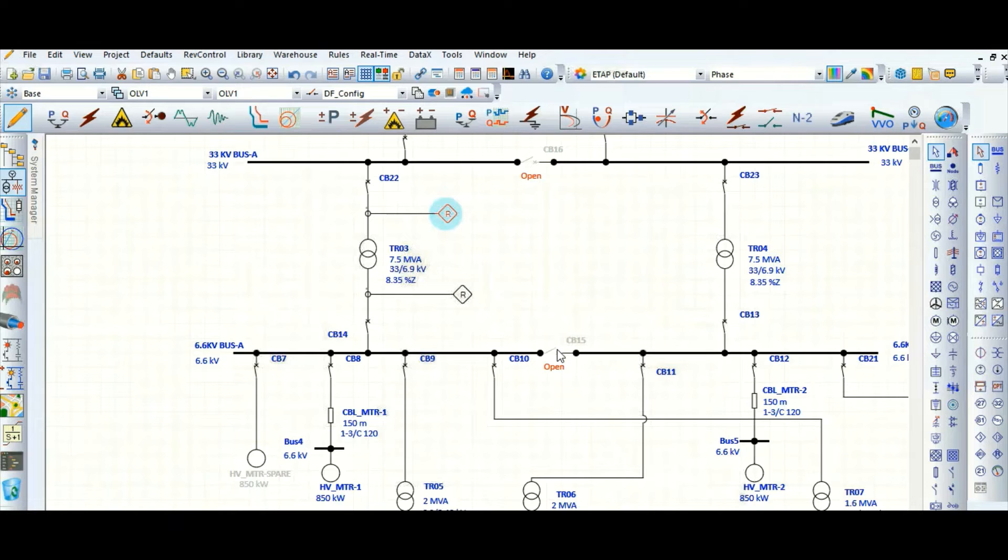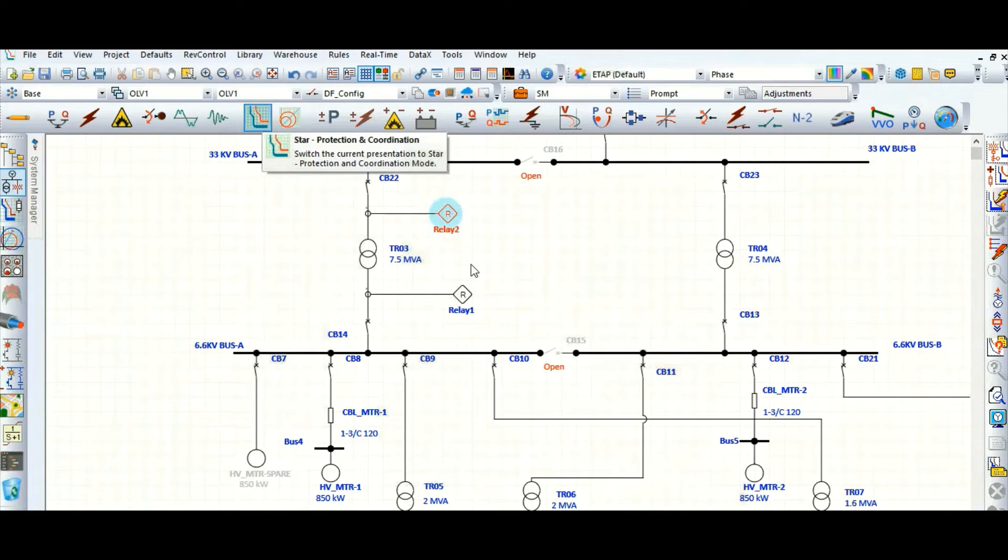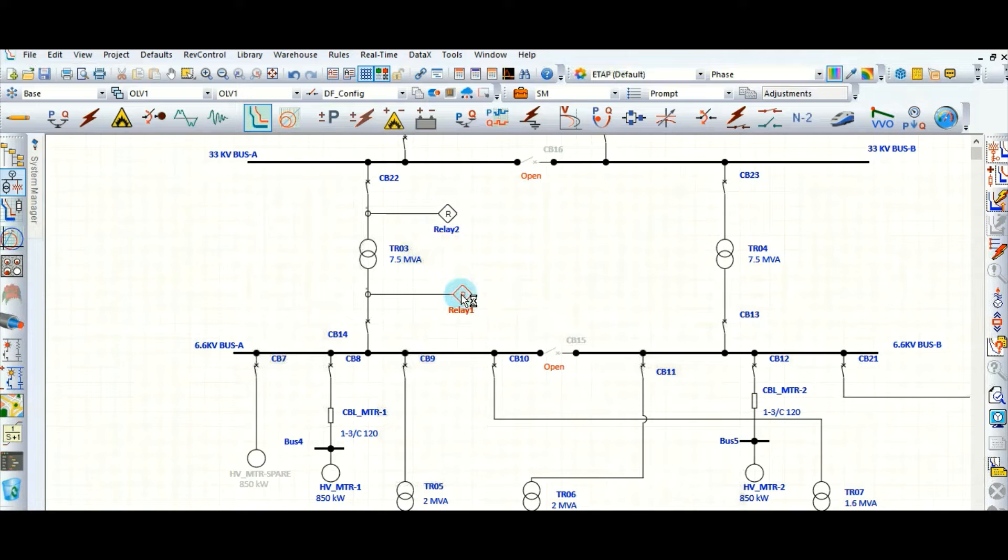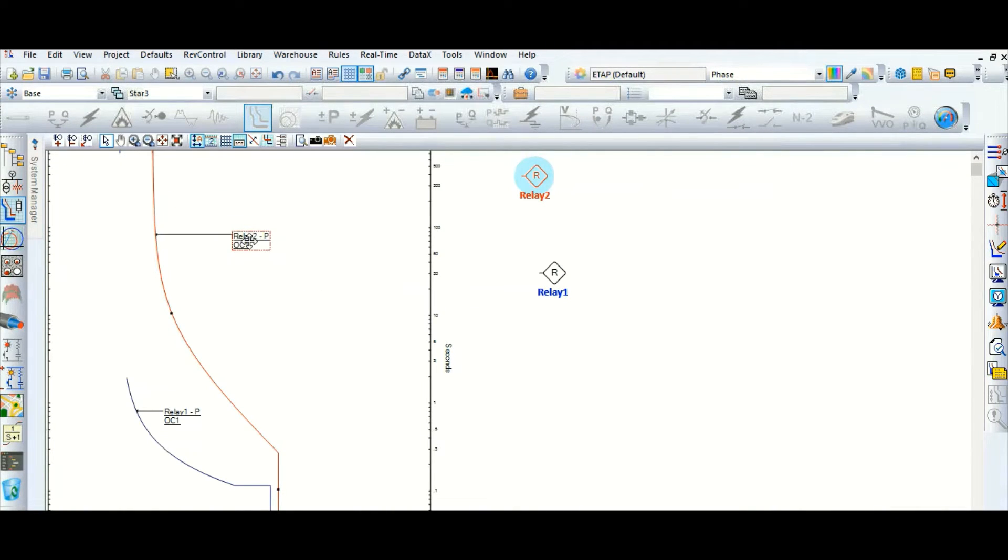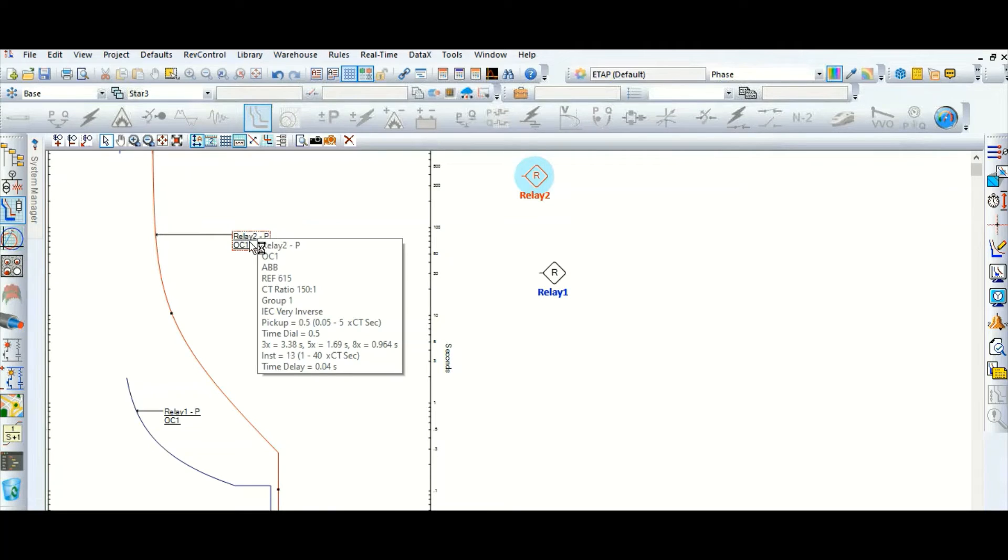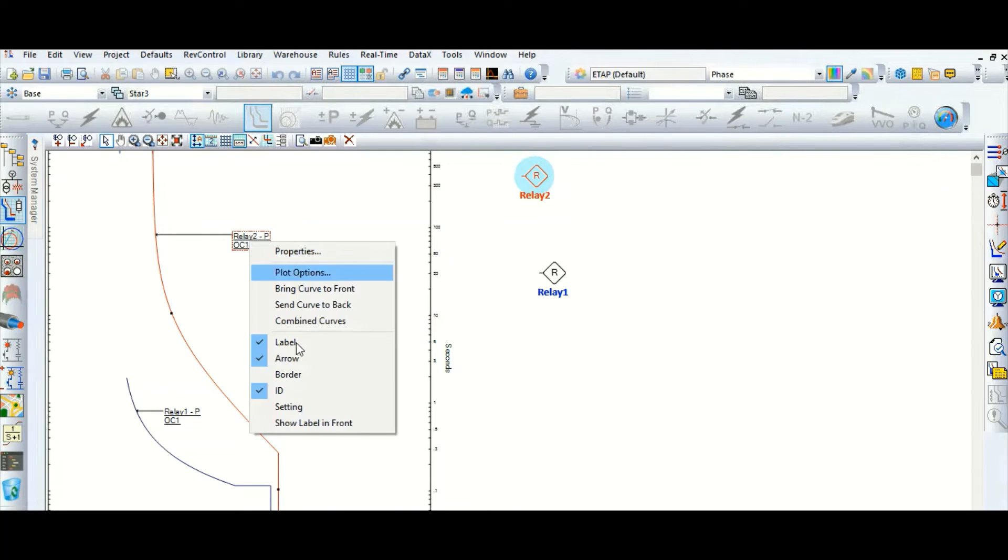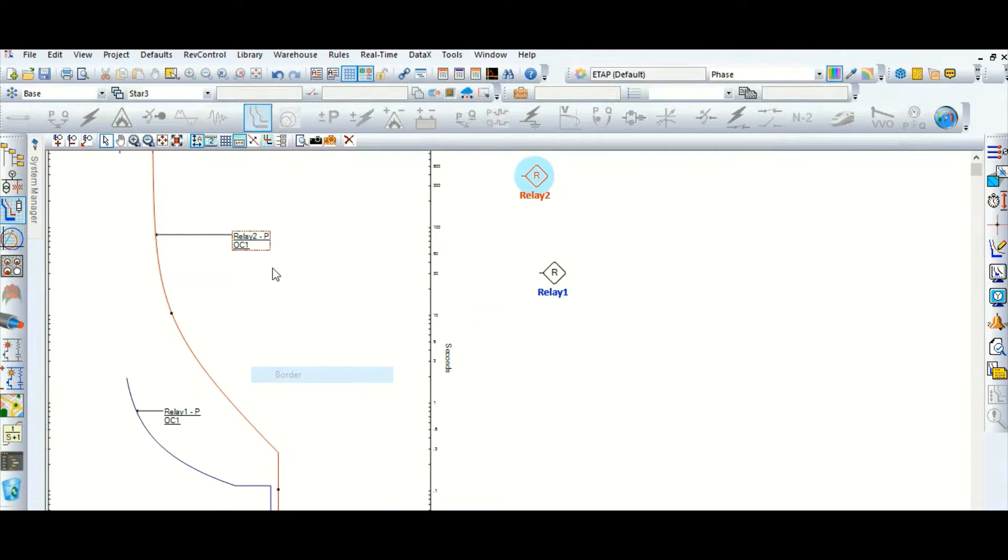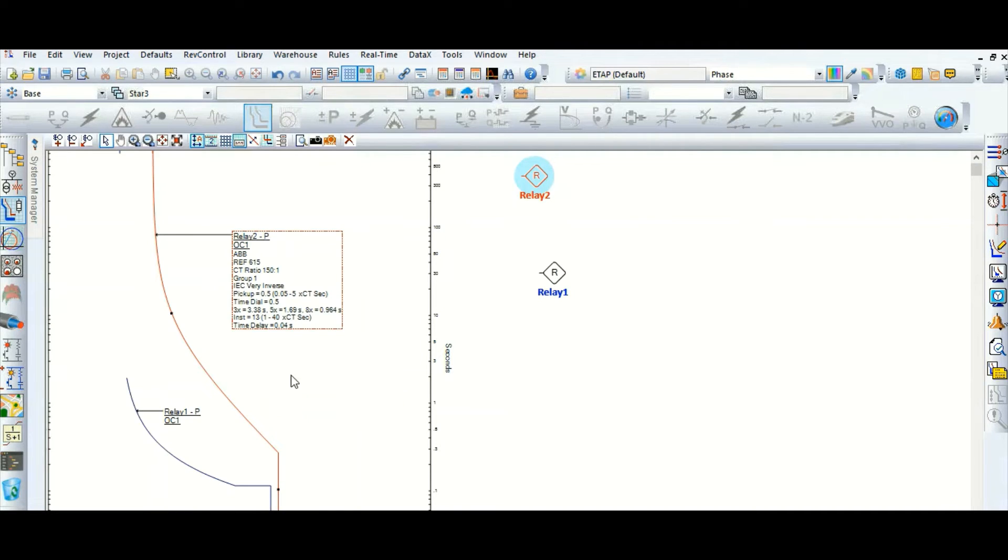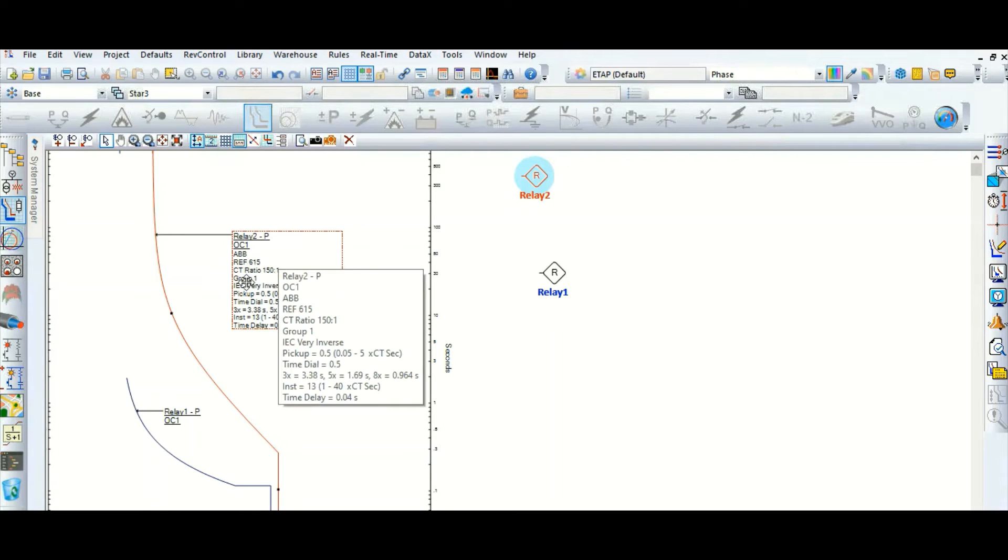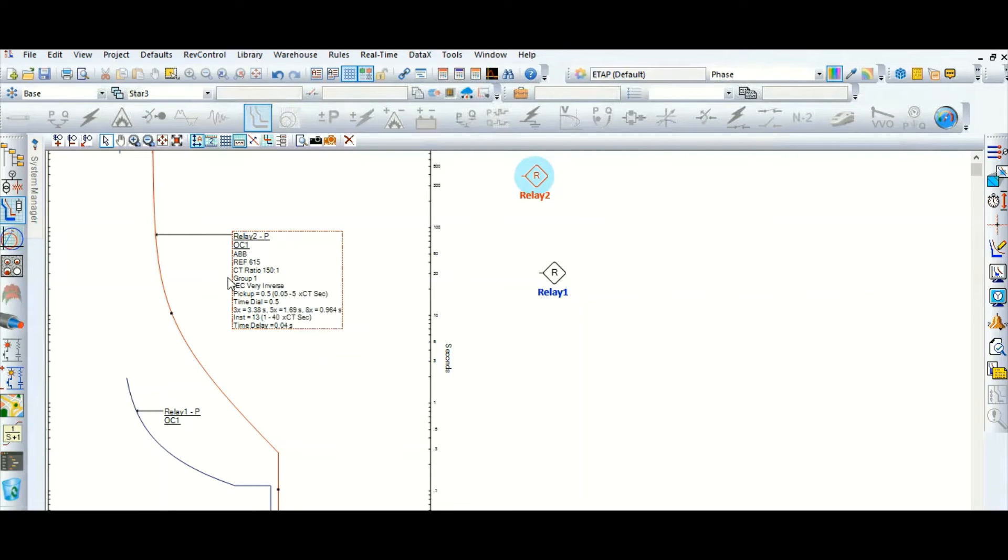Now go to the star mode. Let's check in the TCC curve. This is relay 2, 51 and 50 combined curve. This is REF 615, this is upstream, that means transformer HV side relay 2.